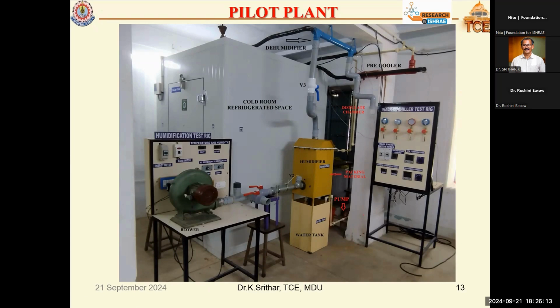The working principle is as follows. The first circuit is the water, which comes from the pump and goes directly to the pre-cooler, where it gets heated by the hot refrigerant. It returns back and is sprayed in the humidifier. The hot water will be cooled down and collected in the water tank. Again, it is circulated. That is the first circuit of water flow.